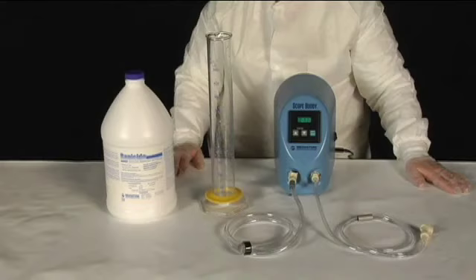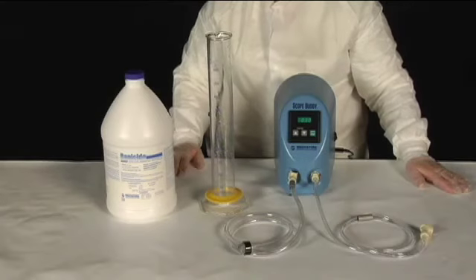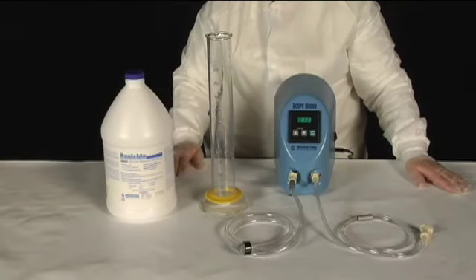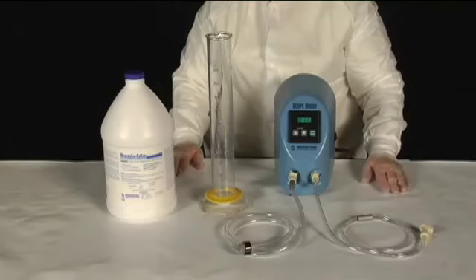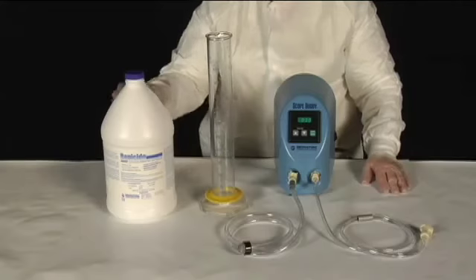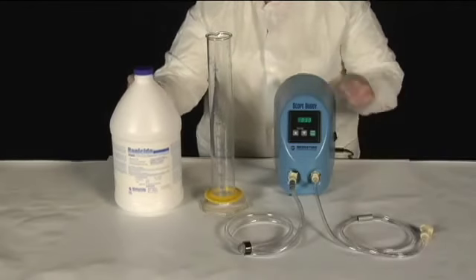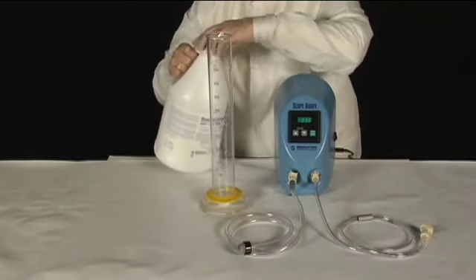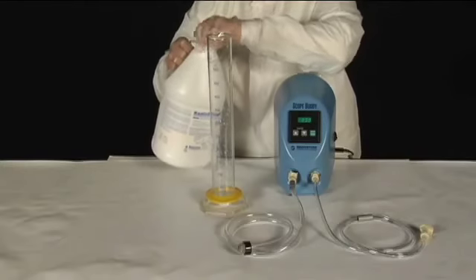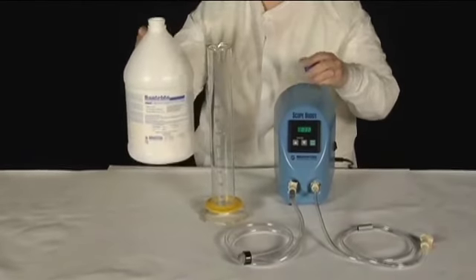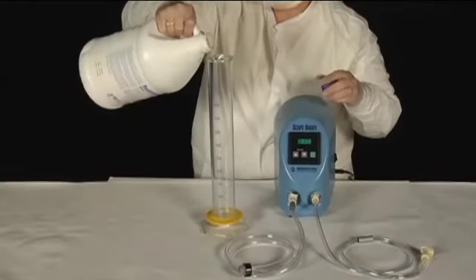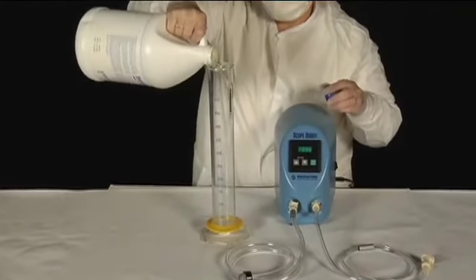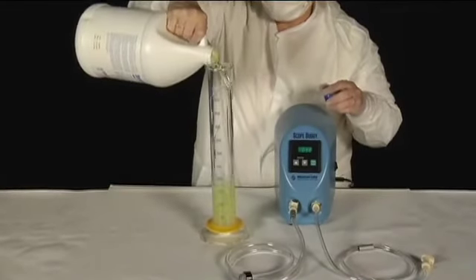The Scope Buddy endoscope flushing aid delivers detergent and rinse water through the channels of contaminated flexible and immersible endoscopes. As a result, Scope Buddy and its associated connection tubing must be decontaminated. Scope Buddy decontamination frequency depends upon the method used to draw cleaning and flushing solutions into Scope Buddy. If solutions are drawn from a sink and recirculated, then Scope Buddy must be decontaminated on a daily basis. If solutions are drawn from a clean and dedicated supply container, then Scope Buddy can be decontaminated monthly.